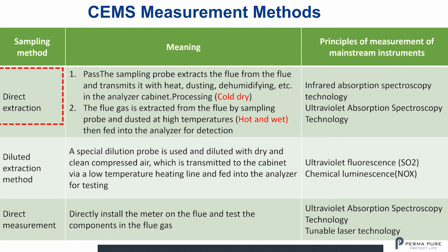So let's look at the main CEMS measurement methods that are out there. The first is the direct extraction method. That's where we mostly play, where the sampling probe extracts from the flue the gas and transmits it with the heat and the dust and all that stuff into the analyzer cabinet. And the system is designed to prepare that for analysis. And you also have 2 different ways, either IR or infrared absorption spectroscopy technology or ultraviolet absorption spectroscopy. Okay. That is the UV absorption is where you can do it hot and wet.